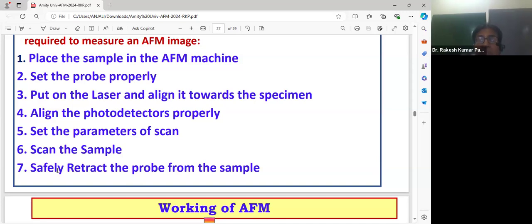So that's why the scanning rate must be slow or moderate. It must not be very fine, very high. And after scanning, safely retract the probe from the sample. This is a very important point. Here we need to take precaution. Very safely we have to retract the cantilever from the sample.